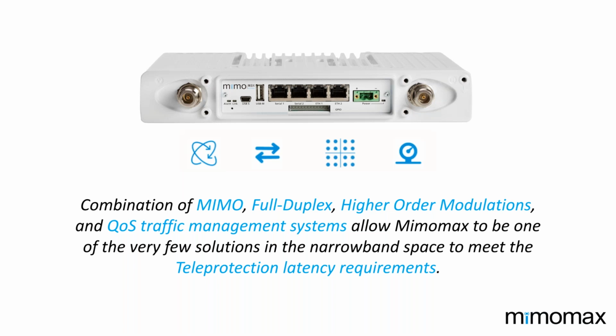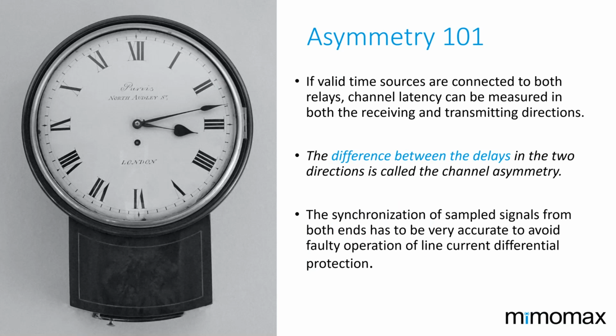Asymmetry relates to the time it takes for an uplink and a downlink, and the delta between those times. We're trying to get the difference in uplink and downlink delay as close as possible. It has to be very accurate for teleprotection schemes, because that delay sometimes determines whether a fault is valid. You don't want a false trip, so you want to get that asymmetry delay as low as possible, otherwise you risk false tripping.